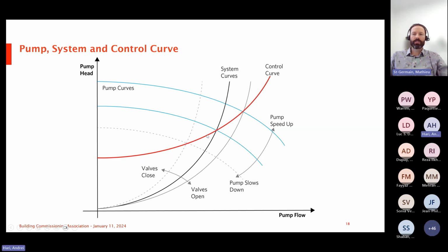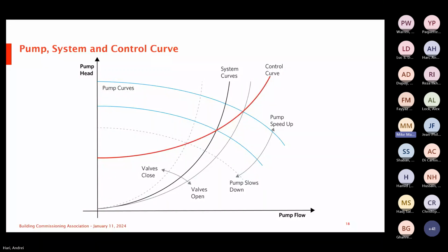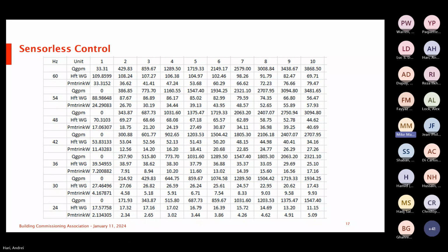Okay. Andrei, there's a question. Go ahead. Yeah. Andrei, I just had that question. You said that the pump can be calibrated in the factory to build that matrix of flow versus power, right? When we take this pump and install it in the field, two questions. Would those parameters change at all because of situational effects in the field? And the second question is, now that we have the pump operating and controlling our system, over a period of time, like 5 years, 10 years out, do those parameters change? Does the pump performance with respect to those parameters change in any way over the life of the pump?